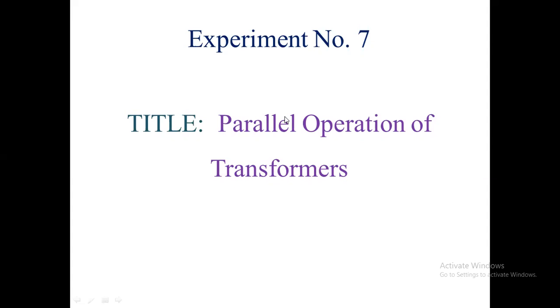That is, we operate two or more transformers in parallel. We have also derived an equation: when the kVA rating of the transformers is equal, we calculated the load shared by each transformer. We also calculated the current shared by each transformer in the theory. Tell me why parallel operation is necessary.